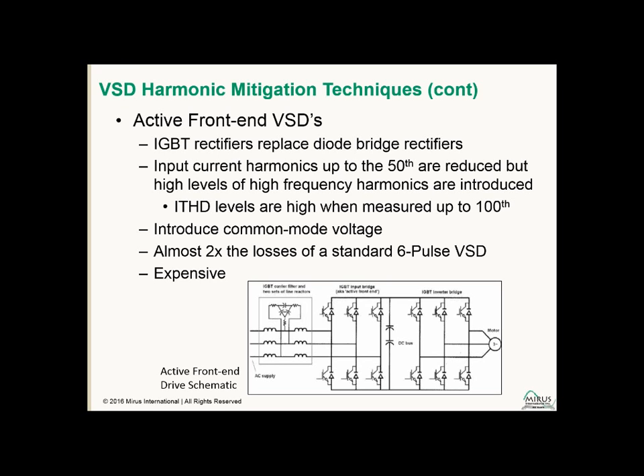There is a paper that we've published that you can find on our website that talks a little bit about active front-end drives and talks about the high frequency harmonics they introduce and compares them to the solution with a passive filter and a variable speed drive. These AFEs also introduce higher levels of common mode voltage. Any variable speed drive will introduce common mode voltages, and that's again the result of the switching of the IGBTs. So all variable speed drives have an inverter section that has IGBTs, and that'll introduce common mode. But an active front end has a second IGBT section, which also introduces common mode. So you're going to have often twice the level of common mode, and that can cause motor problems and other issues on the power system.